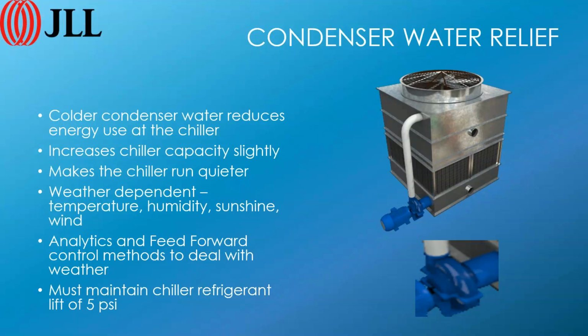Yeah, you're pretty close. The amount of money that you're going to save below 60 degrees starts to become more about artistic merit. So 60 degrees is a pretty good drop off point. There's still some savings below there, but not a bunch. And if you have a condenser pump speed going down to 55% of max, then that's pretty safe. What you can do is you have leaving chilled water and leaving condenser water temperatures. You can monitor that and try and maintain that temperature difference, and use that to control the condenser pump speed, right?